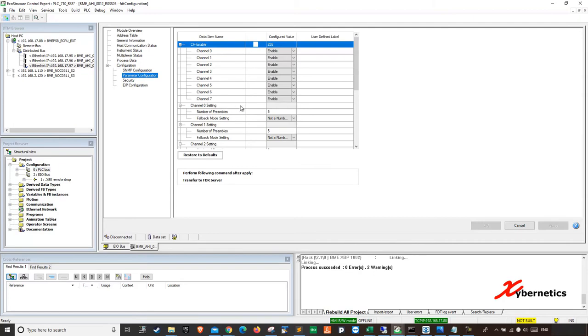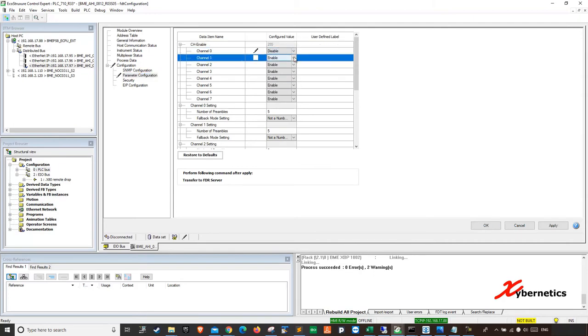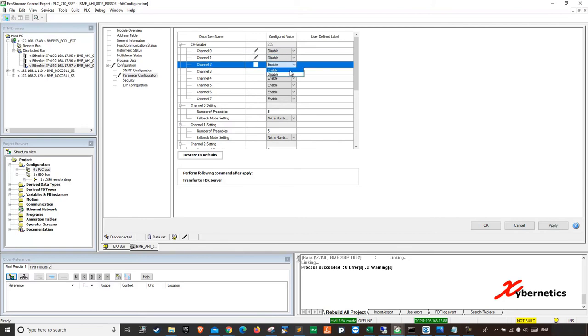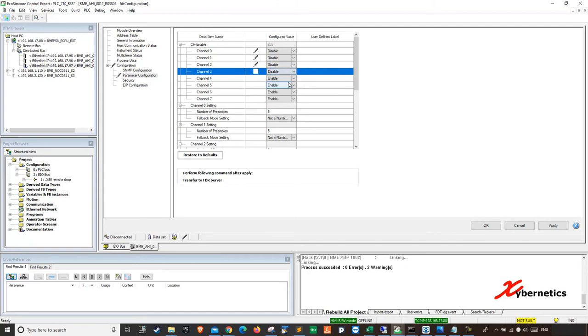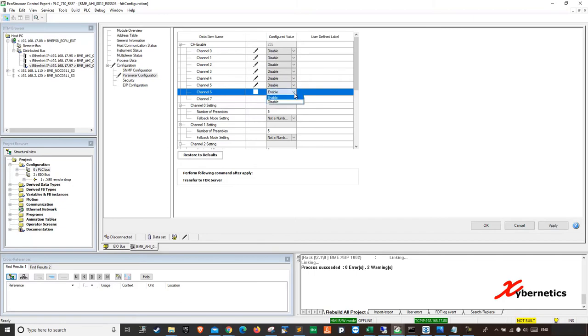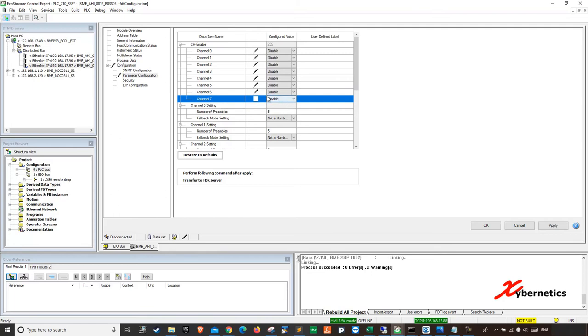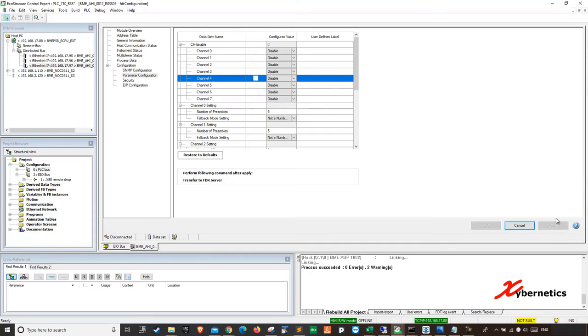Over here, there's got seven channels of HART. You're going to have to disable them. Again, this is only for 4 to 20 milliamps. You have to disable it. If you don't disable it, your 4 to 20 milliamps is not going to work because the device is going to try to talk HART. So make sure there's a pencil sign next to every one of them as you move along. The last one will not have pencil line. Just be careful. Just click anywhere else or hit enter. So you should have all the pencil marking here. So hit apply.